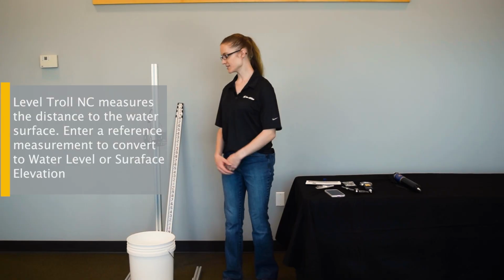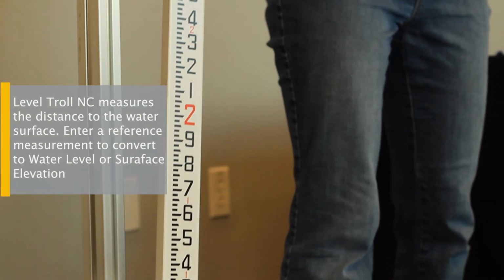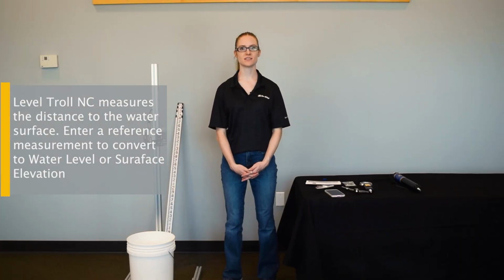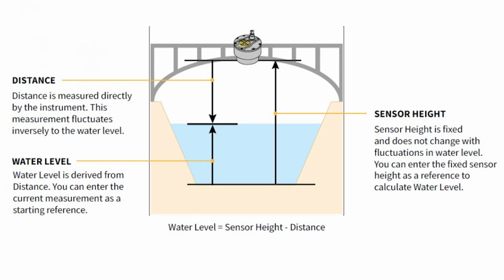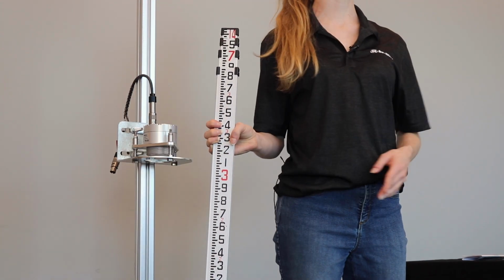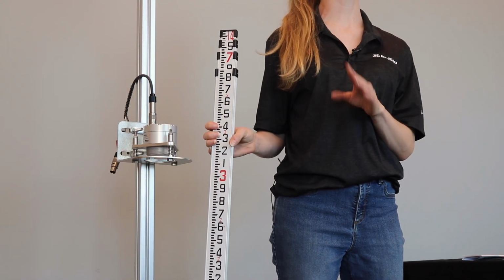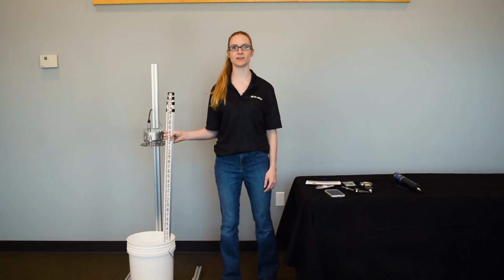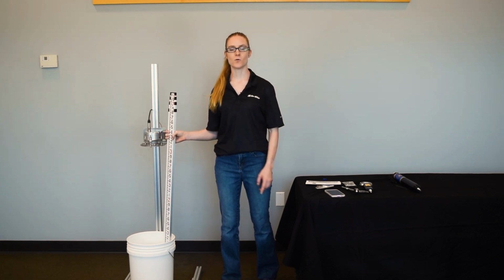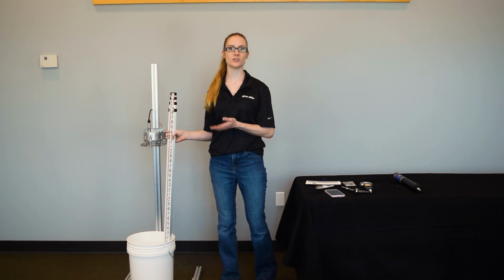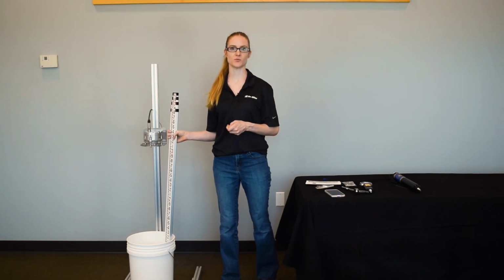The instrument measures the distance from the sensor to the water, so you'll need to enter a reference value to display other measurements like water level above the bottom of the tank or channel, or surface elevation above sea level. For this demonstration, I can use this staff gauge to see that the water level is about 4 inches above the bottom of my bucket. You can measure either the current water surface above your datum or the sensor height above your datum, whichever is physically easiest to measure at your deployment site.